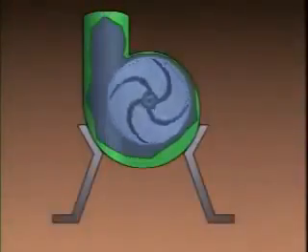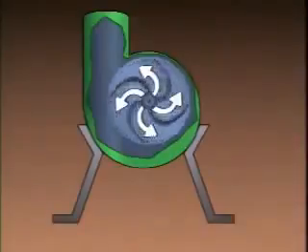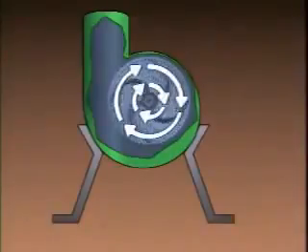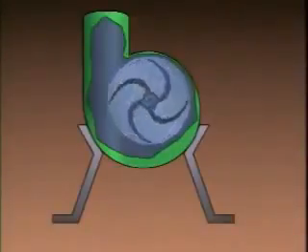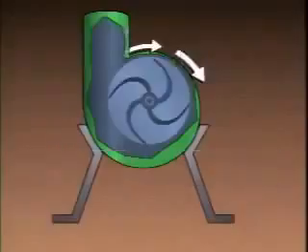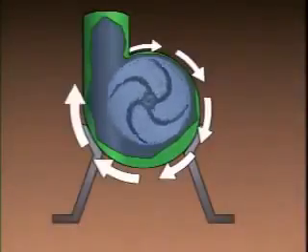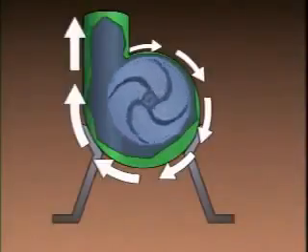Second, it causes the liquid to gain speed. This happens because as the liquid is forced to the outside of the rotating impeller, it must move faster to keep up with the impeller. As the liquid flows away from the impeller, it spreads out to fill the volute. The expansion in the volute causes the liquid to slow down and its pressure to increase. The increased pressure moves the liquid through the discharge of the pump and on through the piping systems of the process.